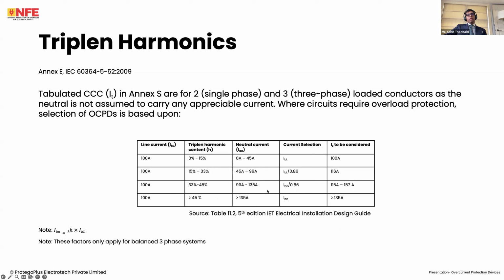In excess of this, same story there, but we do not apply this 0.86 value because, like I said, the current flowing in the line conductors is such that it is no longer at the full current carrying capacity of the line conductor. So we can forget about this 0.86 factor.